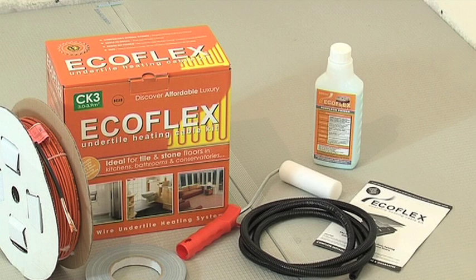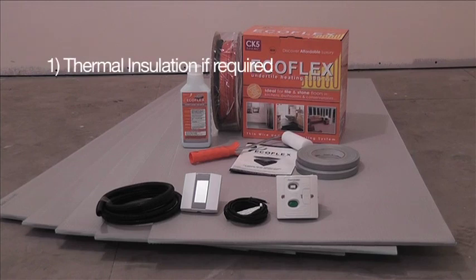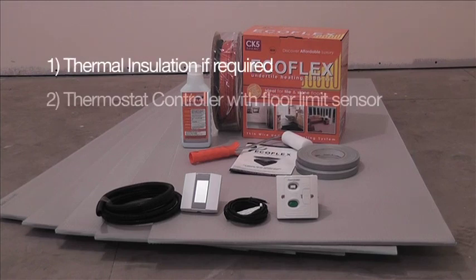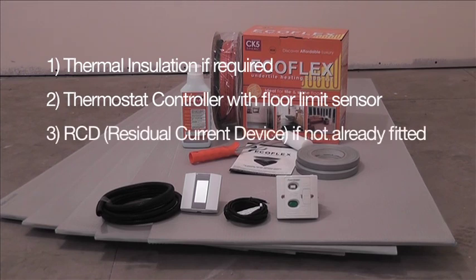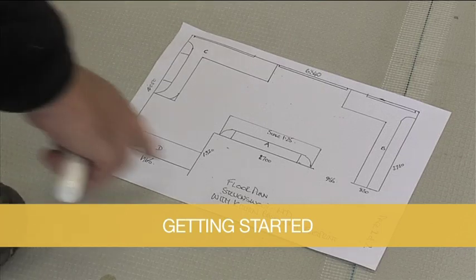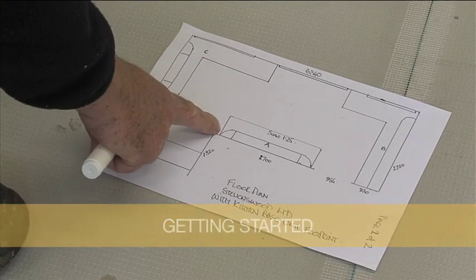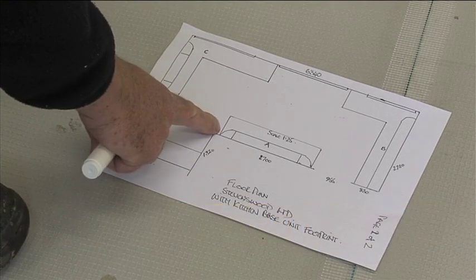You will require the following accessories to install the heating system: thermal insulation if required, a thermostat controller with floor limit sensor, and RCD if not already fitted. Before commencing laying the ECOFLEX heating cable, plan your installation using a sketch, marking your laying pattern and planning the positions for the wall-mounted thermostat, floor probe and junction box.